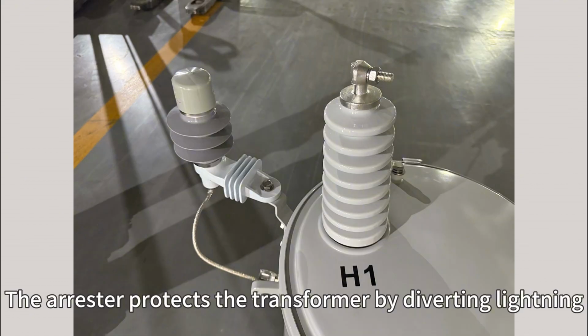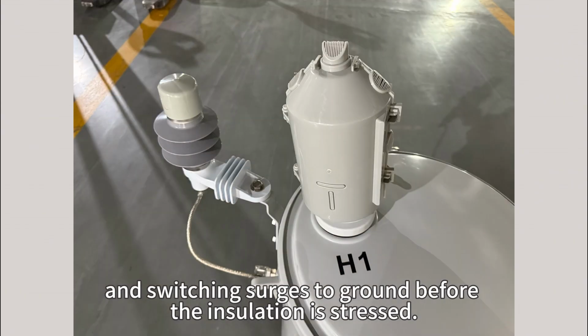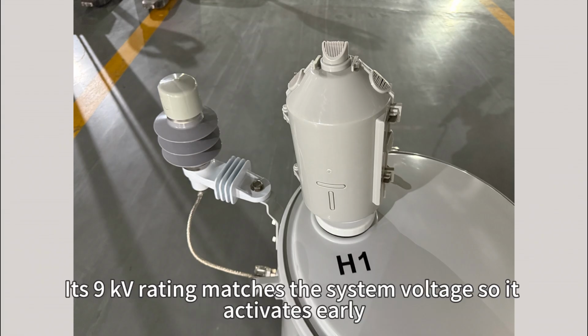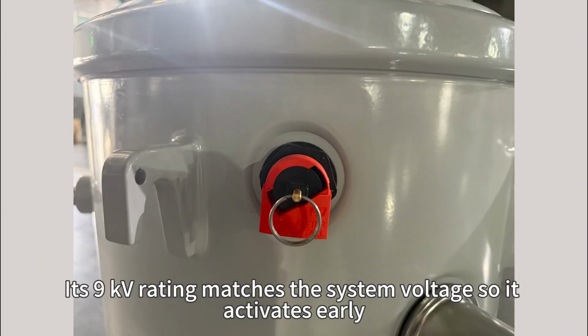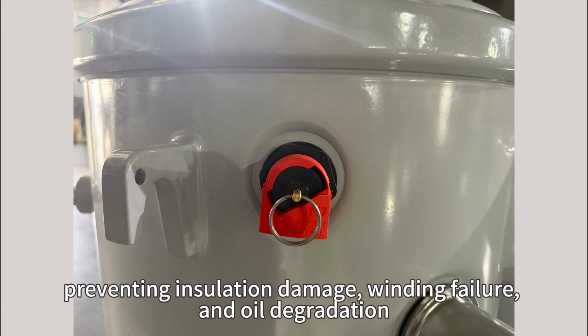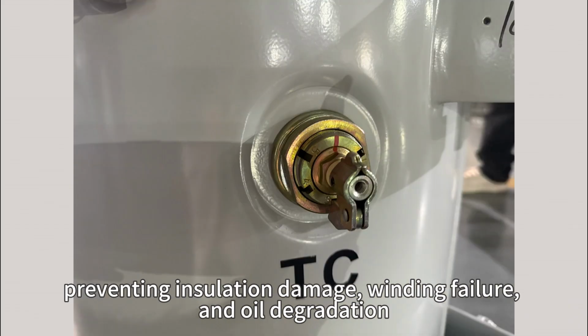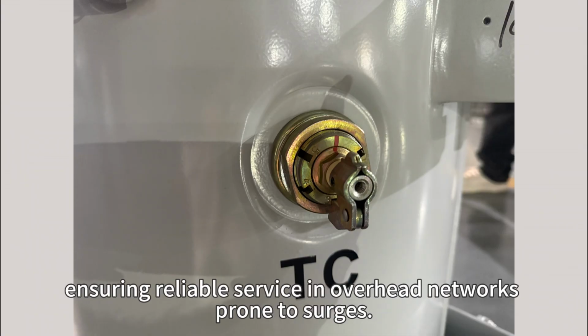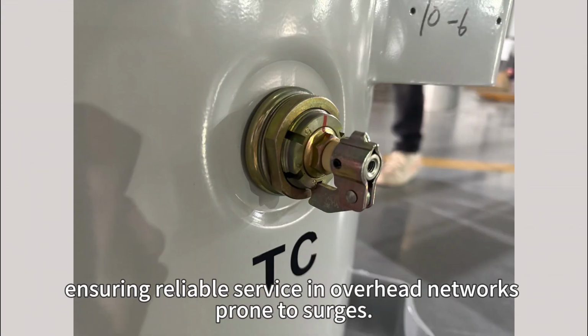The arrestor protects the transformer by diverting lightning and switching surges to ground before the insulation is stressed. Its 9 kV rating matches the system voltage, so it activates early, preventing insulation damage, winding failure, and oil degradation, ensuring reliable service in overhead networks prone to surges.